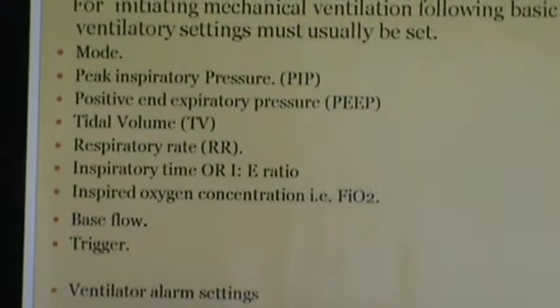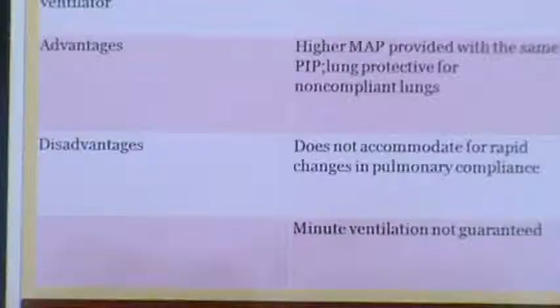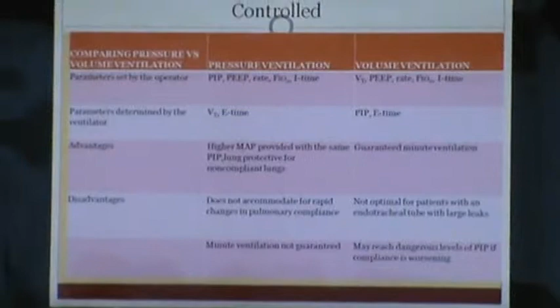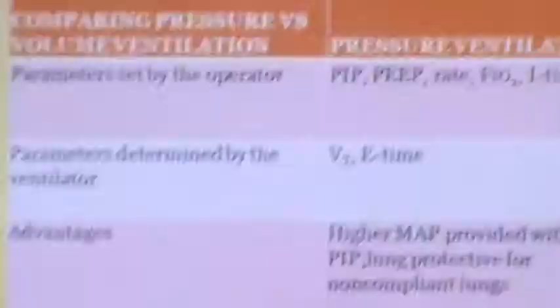Depending on the mode of ventilation, we are selecting pressure limited or volume limited. In pressure limited, tidal volume and minute ventilation will vary, and we have to set these parameters. In volume limited ventilation, we have to set these parameters, and PIP and mean airway pressure will vary. This is the big difference between pressure ventilation and volume ventilation. In pressure ventilation, tidal volume will be decided by the ventilator, and in volume ventilation, the PIP will be decided by the ventilator.